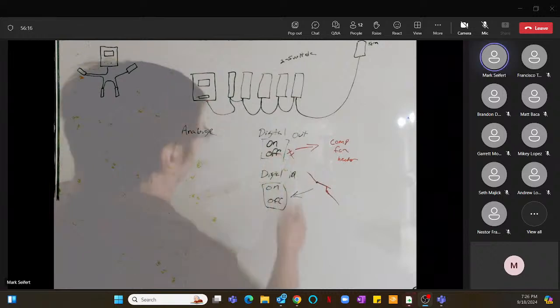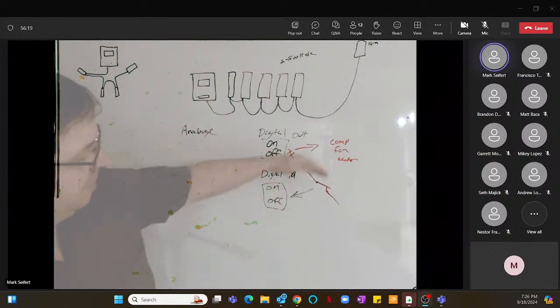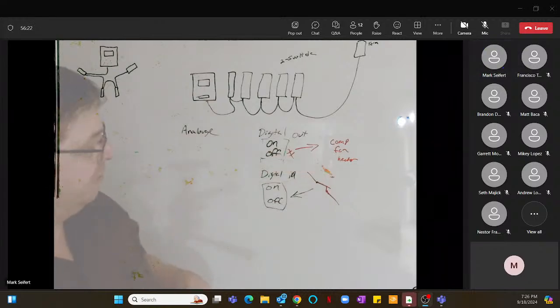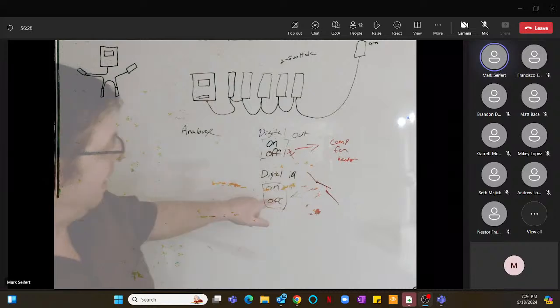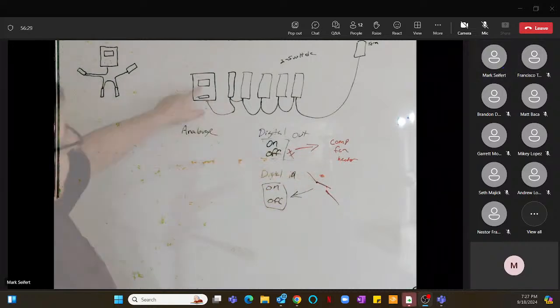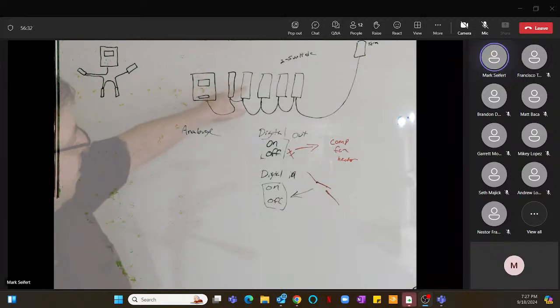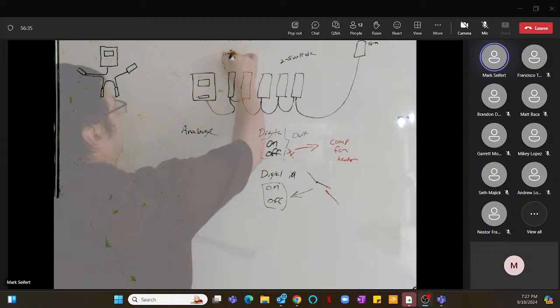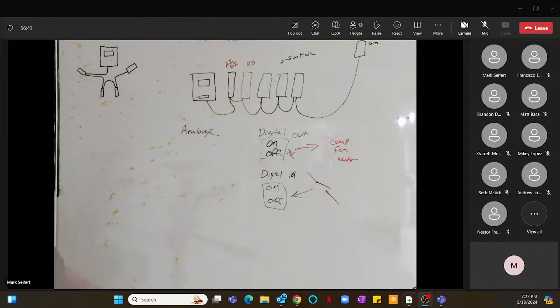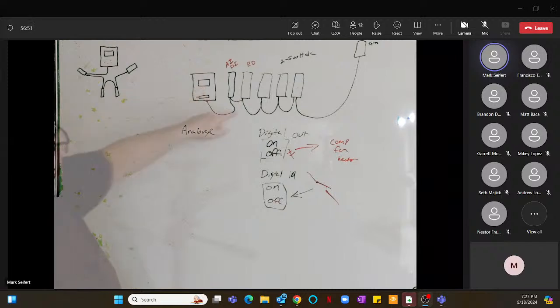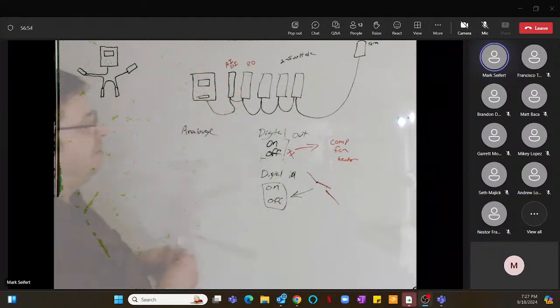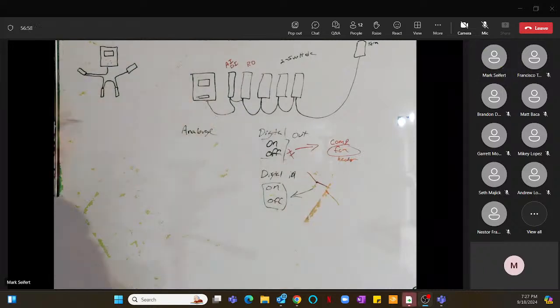So digital out. Let's say the digital in is a door switch, okay? It's open, meaning it's off, which will turn the fan off using the computer brain in a board. So let's call this the AI-DI board, and this is the RO. Door switch is open, tells this board, hey, I'm open, tells the brain, hey, you're open, sends a signal out through here to the RO, you better open, because we need to shut this fan off. Okay, that's it, that's all it is.